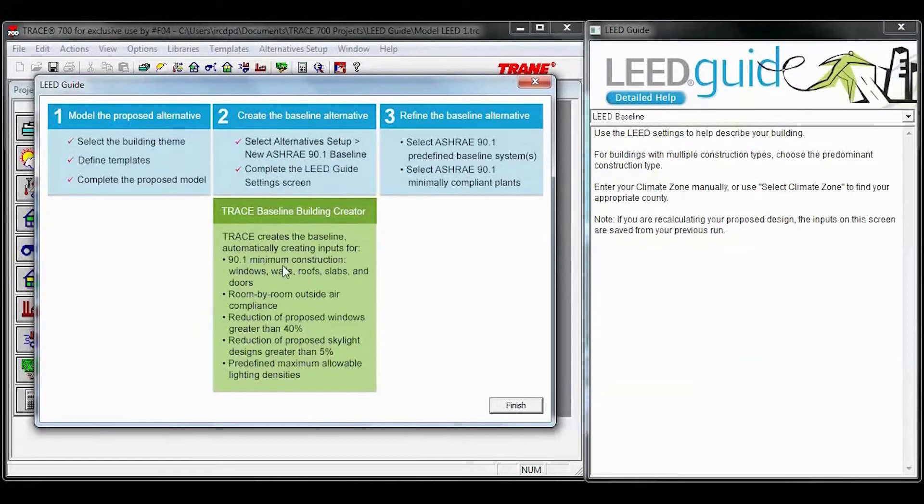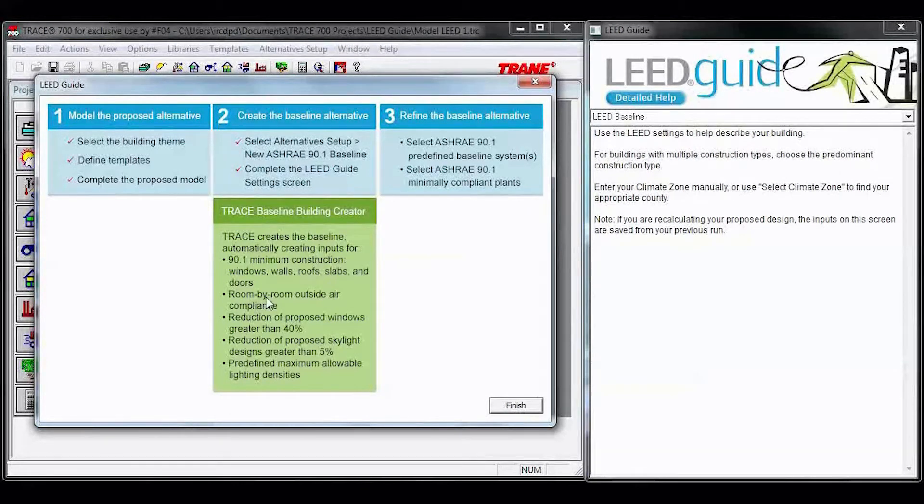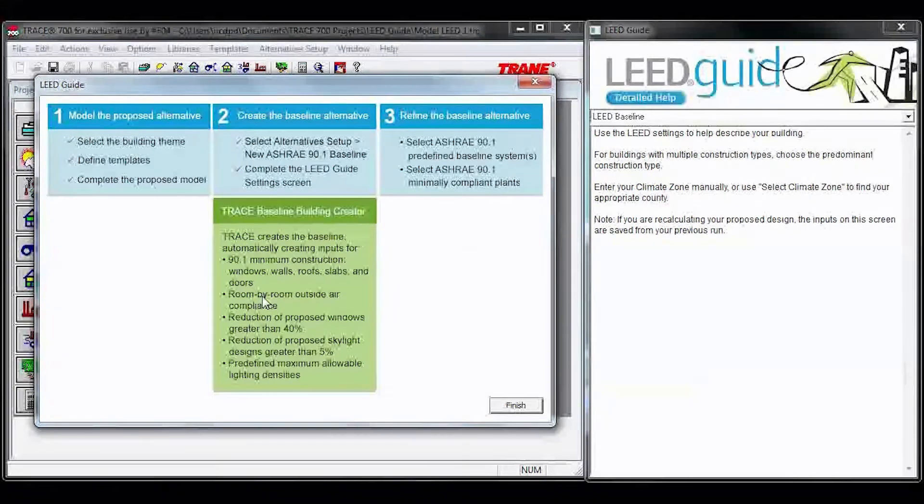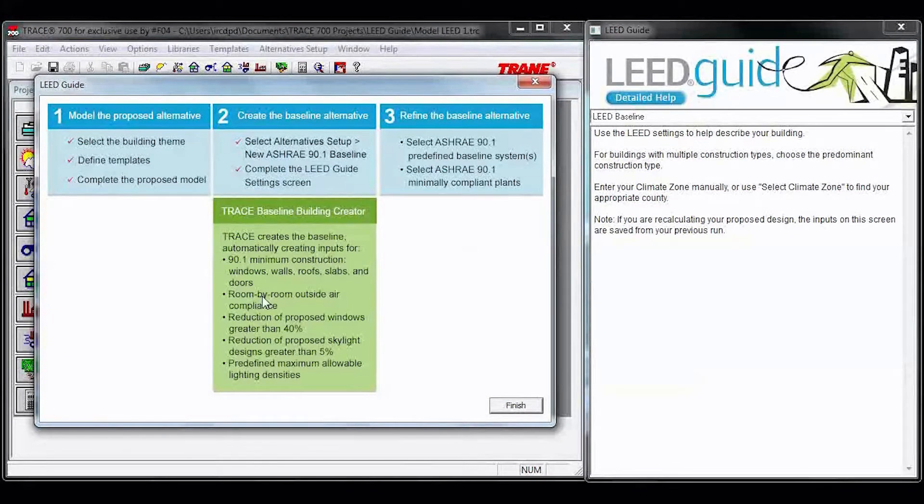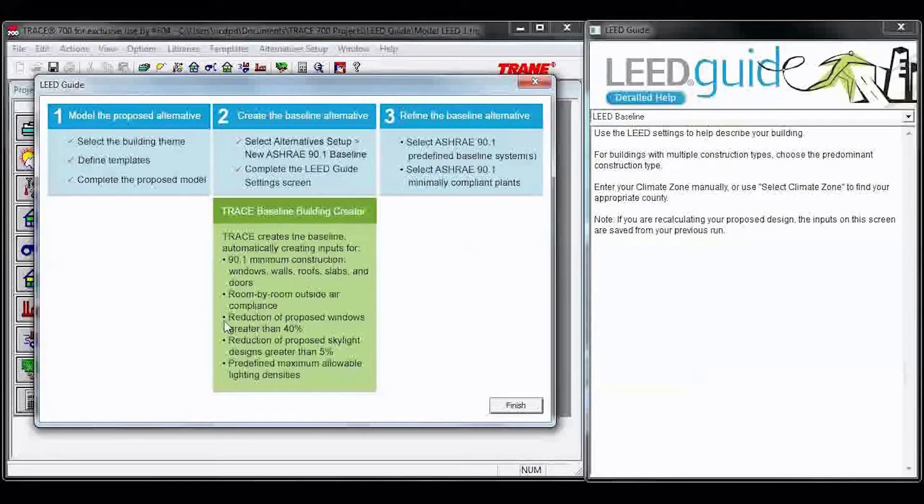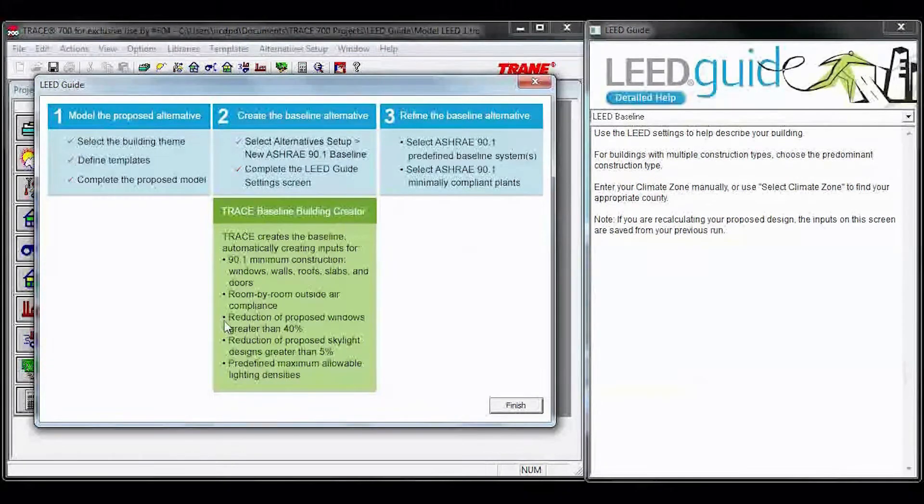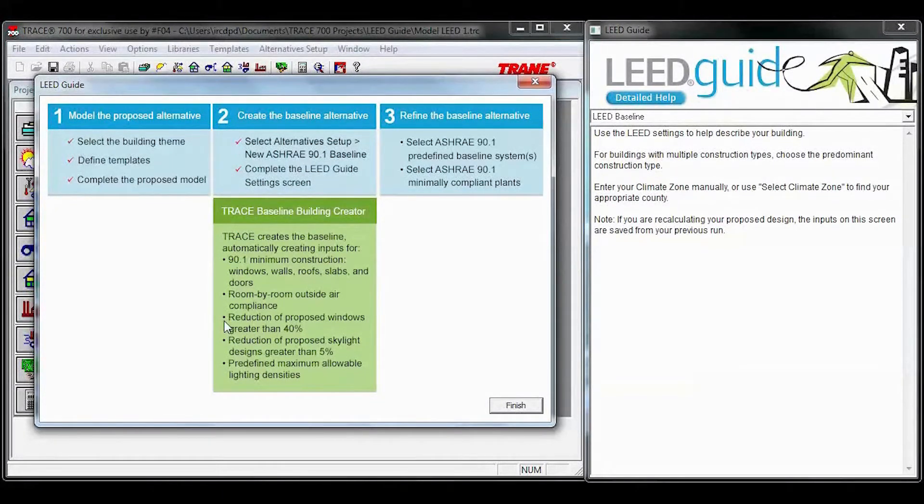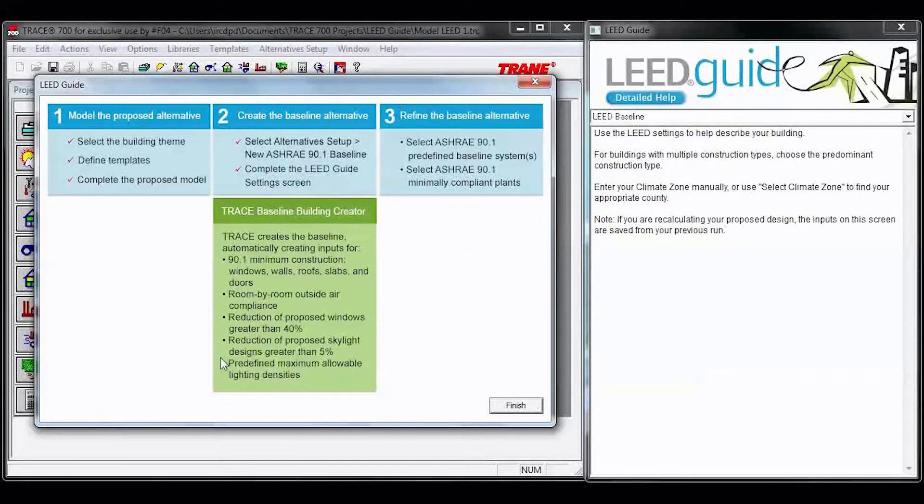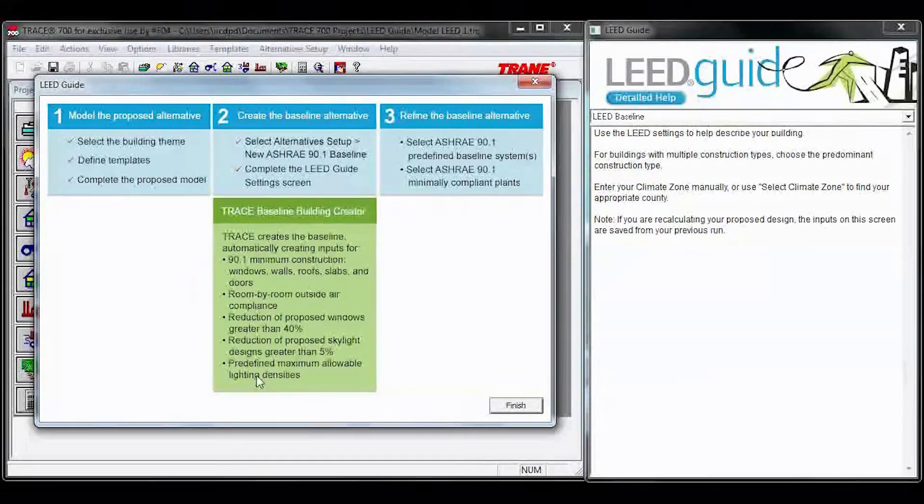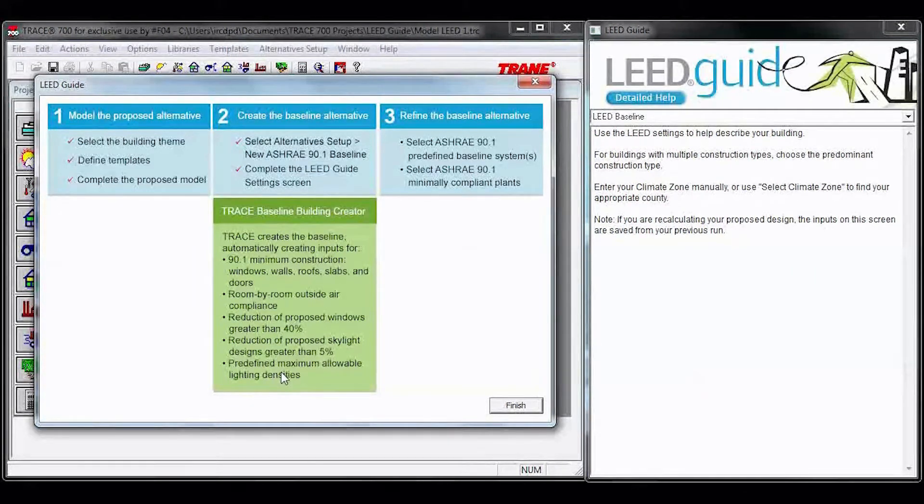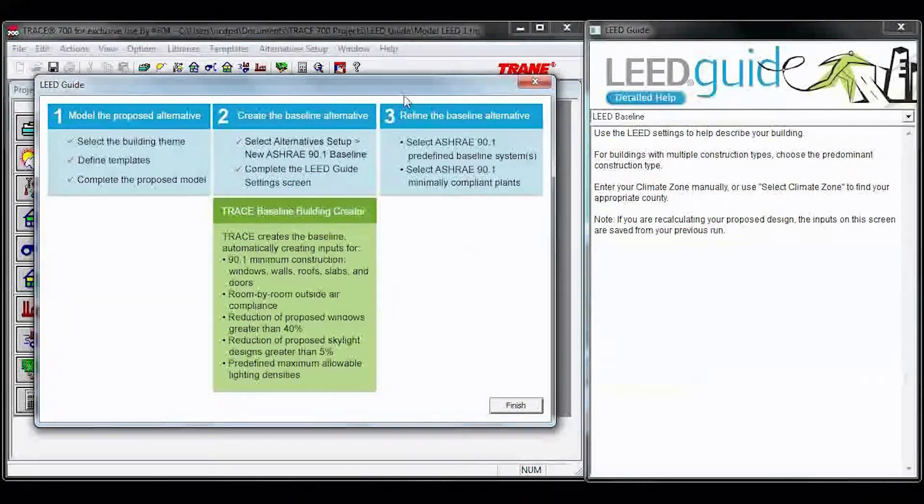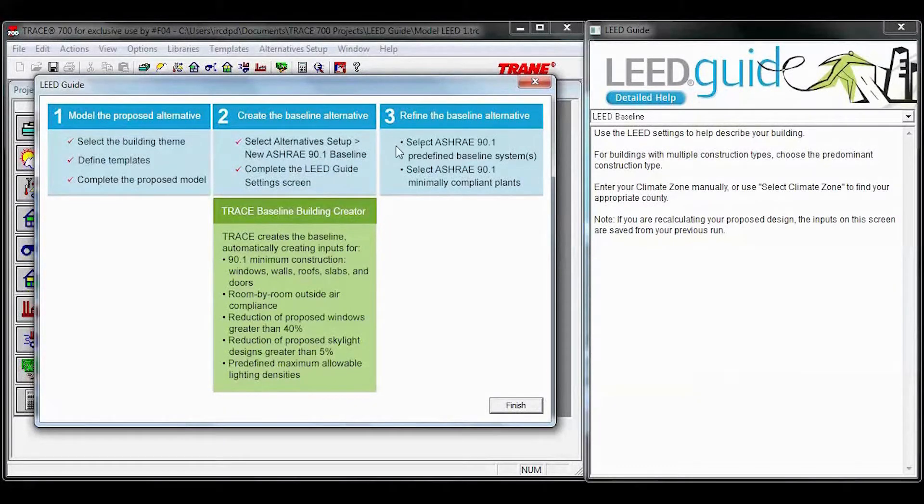We've used 90.1 minimally compliant construction types. We've gone room by room, and we've input your outside air based on your proposed. We've gone through and we've reduced the total building window percentage if it's greater than 40% down to 40%. We've reduced the skylights down to 5% if they exceeded, and we've predefined maximum allowable lighting densities.